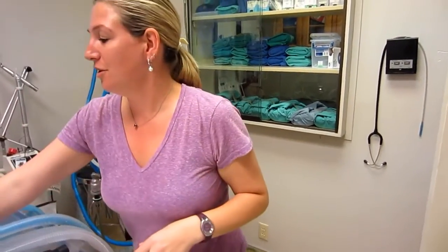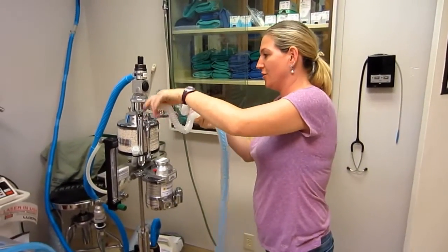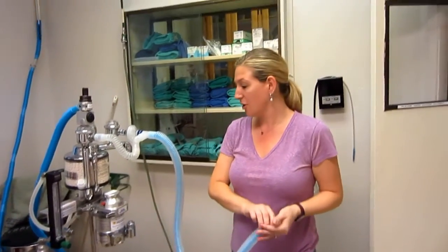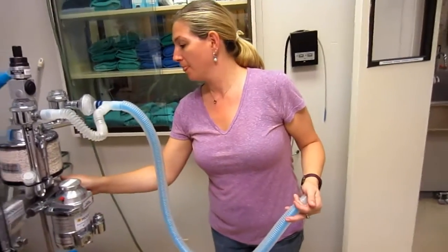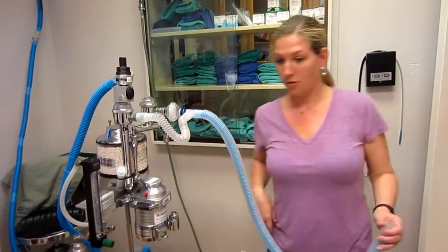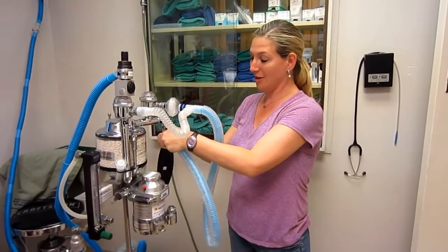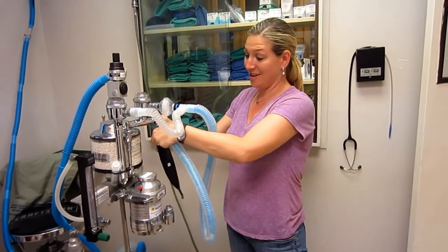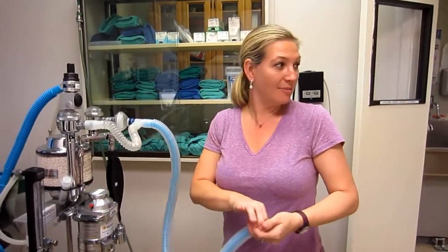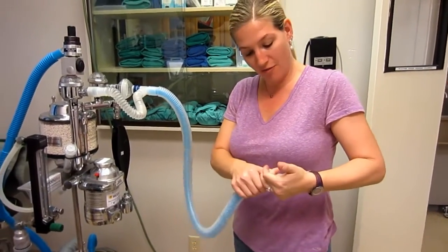I'm going to hook up our rebreathing system so that I can show you how to do a pressure check for this as well. Now I'm going to make life a little easier on me, I'm going to use a 1 liter bag because it's not as much to fill up as a 3 liter bag. So again, this becomes a little bit difficult to find the seal, but you find a seal here.